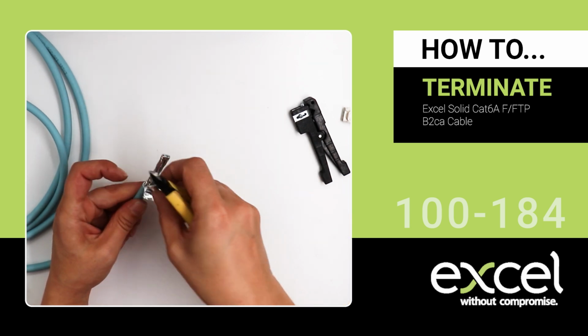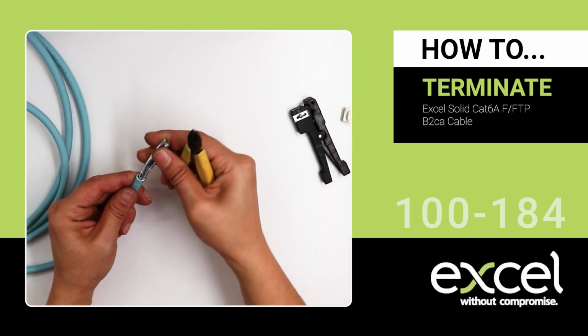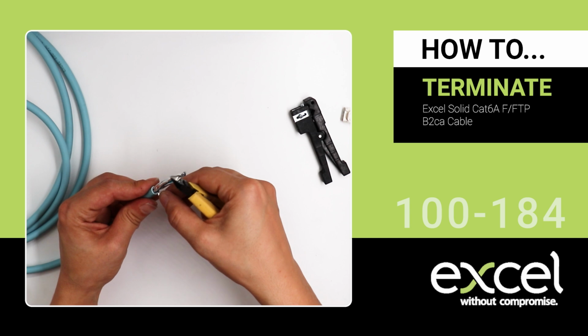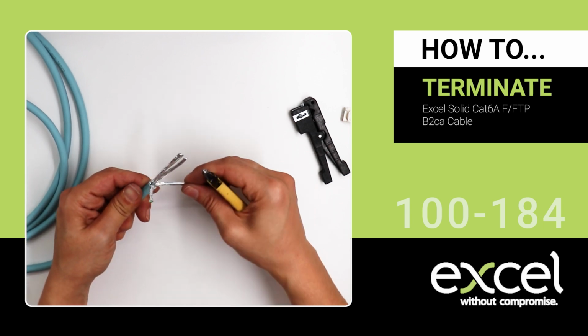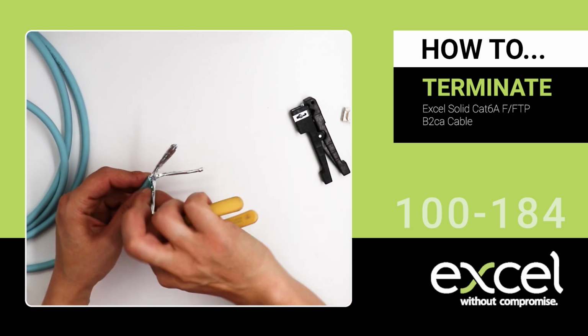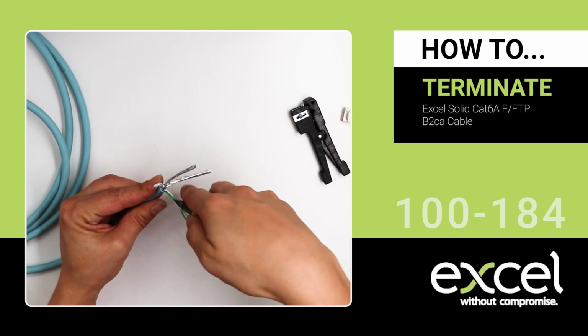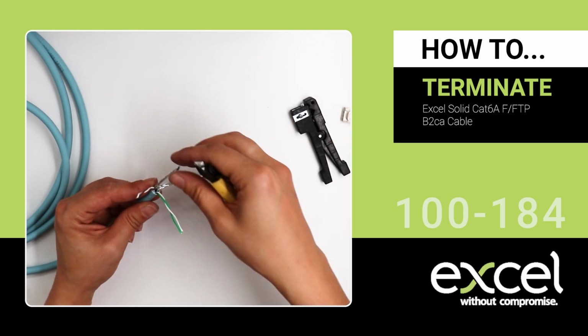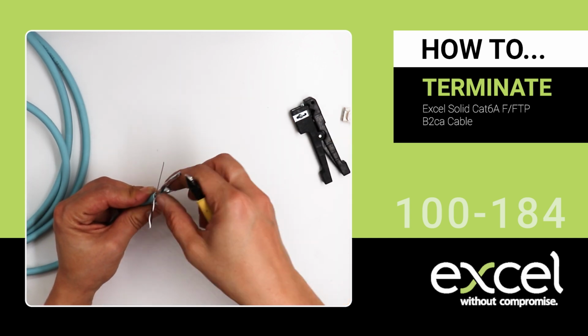Snip and remove the outer foil layer using the side cutters. Then snip the foil from the pairs with the side cutters. Be careful not to cut the drain wire. Unwrap the foil and remove it from the individual pairs of cable.